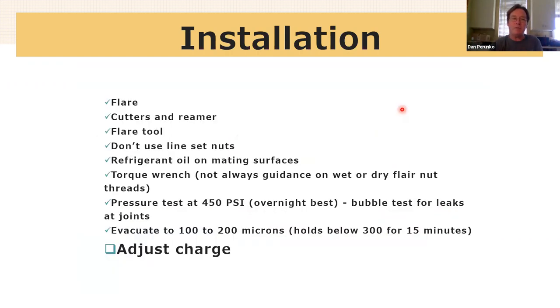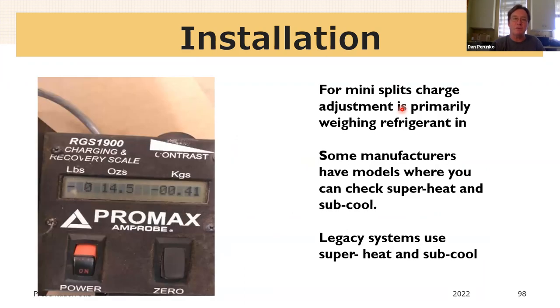And then after all that has passed, you release the refrigerant into the system and adjust the charge. For mini splits, the higher efficiency option, you use weight. So there's a bottle on a scale. This is a picture of a scale. And in this example, 14 ounces of refrigerant have left the bottle and gone into the system, right? So decrease in weight on the scale is an increase in weight in the system.